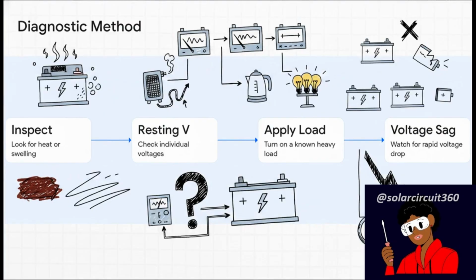Here is the proper systems engineer way to do this. Step 1, start with your eyes. Look for obvious signs: swelling, discolored terminals, or melted insulation. Step 2, check the resting voltage of each individual battery. If one is low, yeah, that's highly suspicious. But do not stop there. Step 3 is the real test. Apply a known, steady load. Think a resistive heater or a really heavy bank of shop lights. Step 4, while that load is running, watch for rapid voltage sag on each battery. The healthy ones, they'll hold steady, but the dead cell's voltage will tank fast. Boom, you've just caught your invisible killer red-handed.